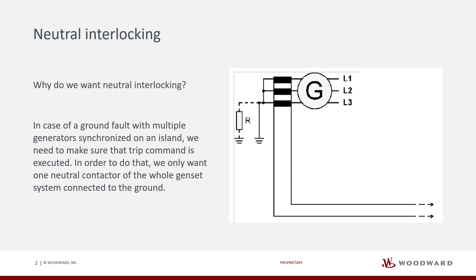Why do we want Neutral Interlocking? In case of a ground fault with multiple generators synchronized on an island, we need to make sure that trip command is executed. In order to do that, we only want one neutral contactor of the whole genset system connected to the ground.